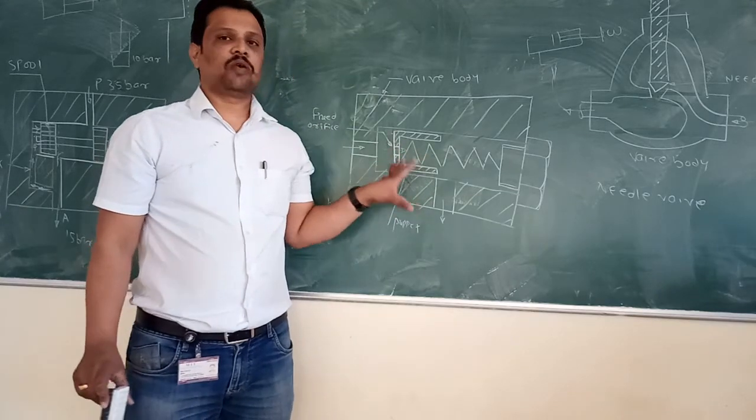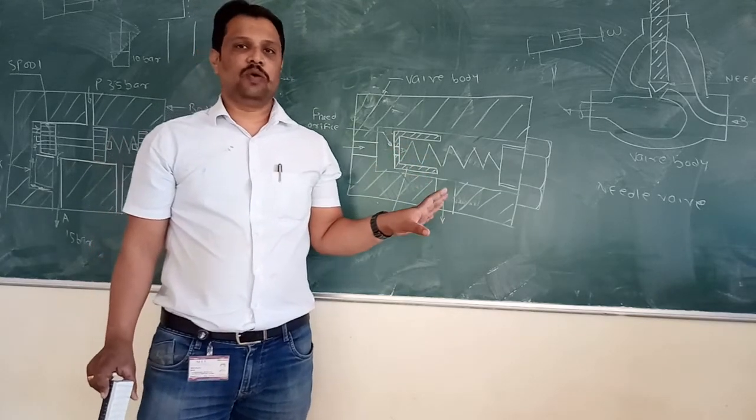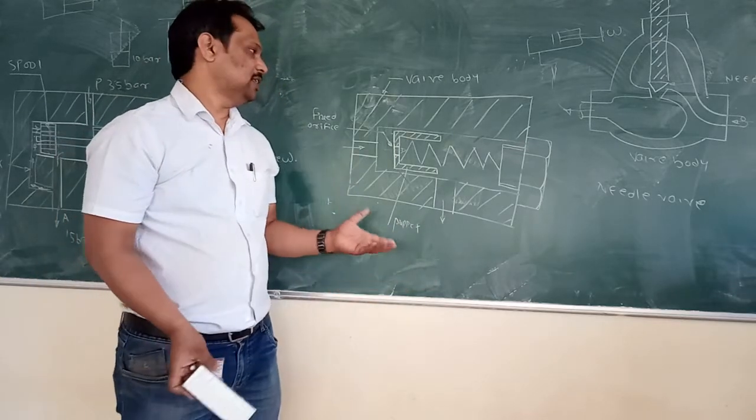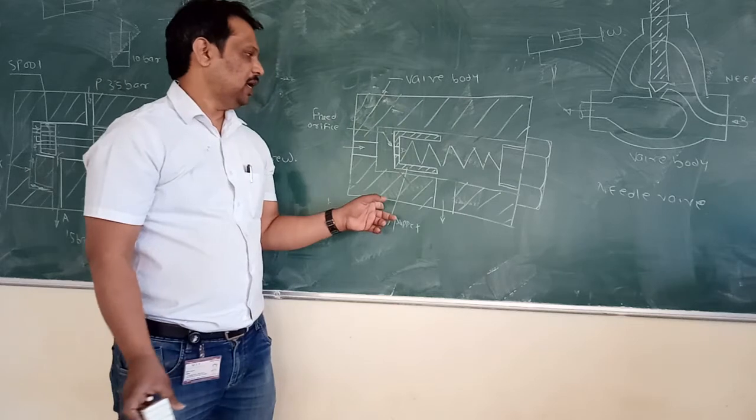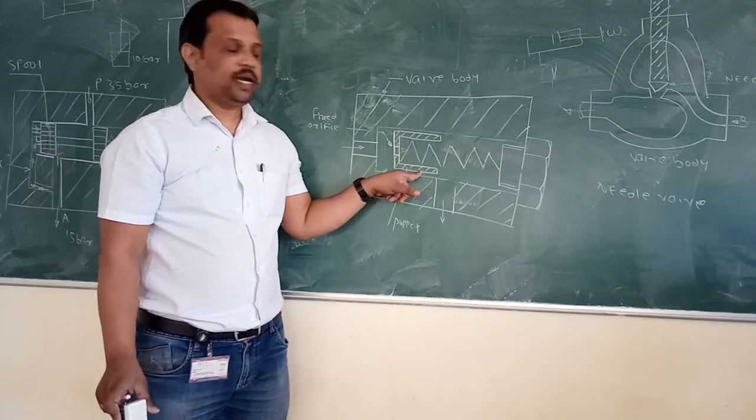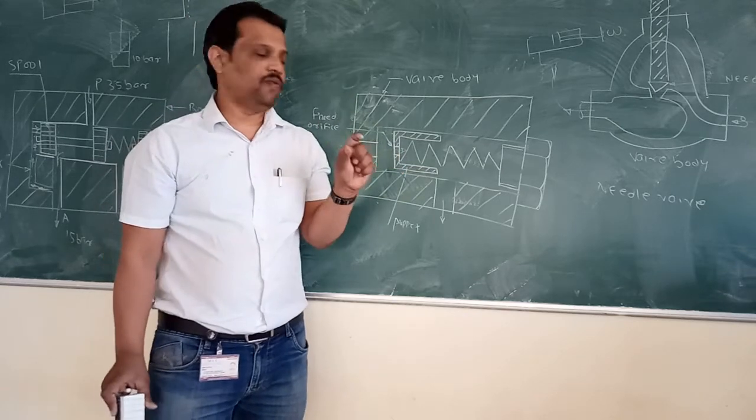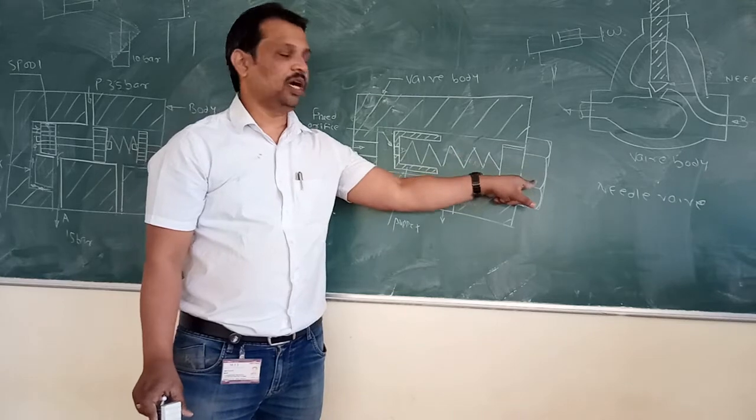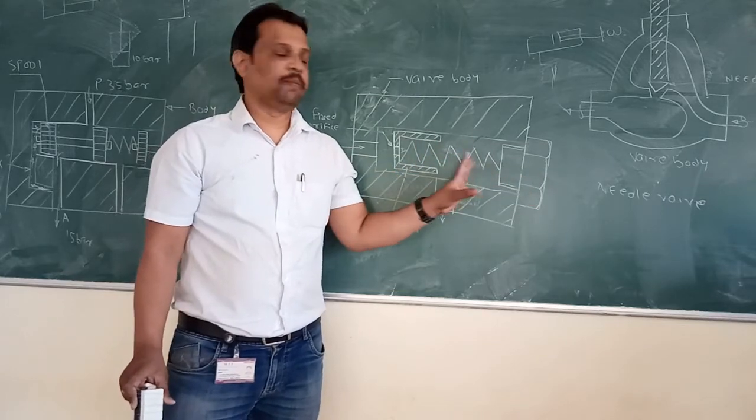This is Pressure Compensated Flow Control Valve. So, start with the construction. In construction, there is a valve body in which there is a hollow bore, in which hollow poppet with one fixed orifice. This poppet is mounted on spring and there is a nut for adjusting of this spring pressure.